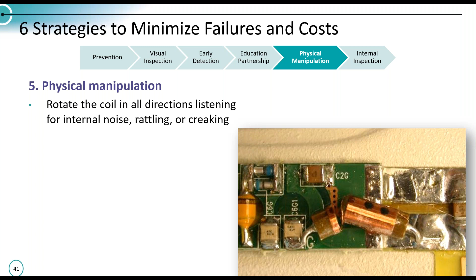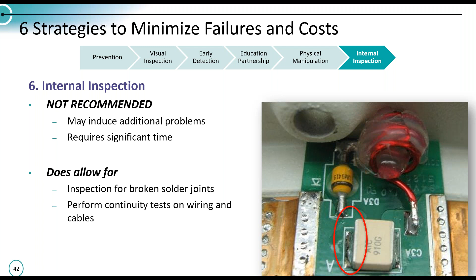Innovatus does not recommend that you perform any kind of internal inspection of your MRI coils, because you can actually induce an additional problem or many additional problems, and it can require significant time to inspect all of the components inside. You'll realize you're going to be looking for broken solder joints, and you can perform some continuity tests on wiring and cables in the field if you absolutely feel you must. To give you an idea of what you might encounter, here are some broken solder joints - in the photo on the left-hand side, we're talking about a quarter inch, an eighth of an inch area that's just been greatly magnified.